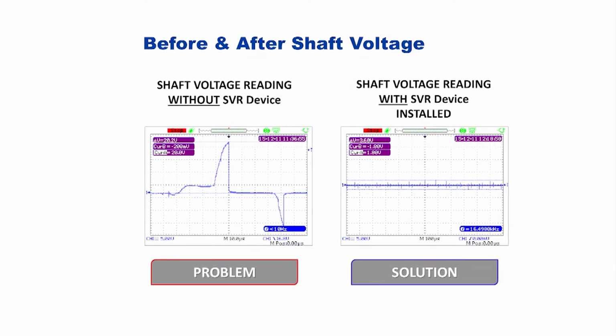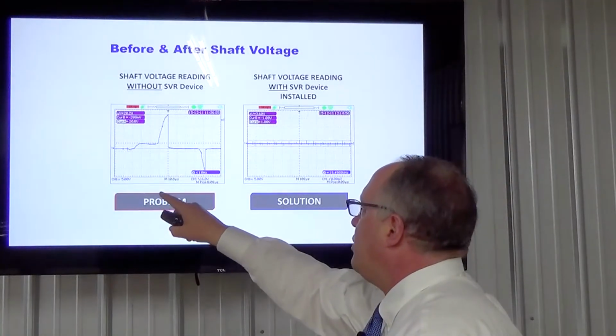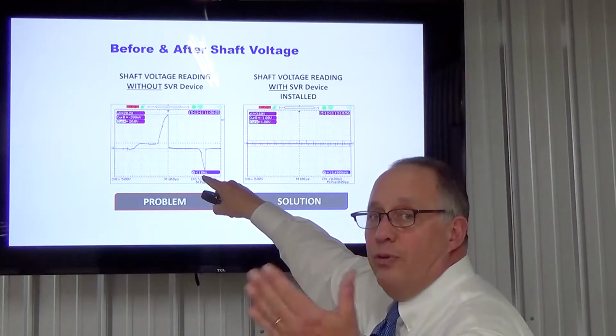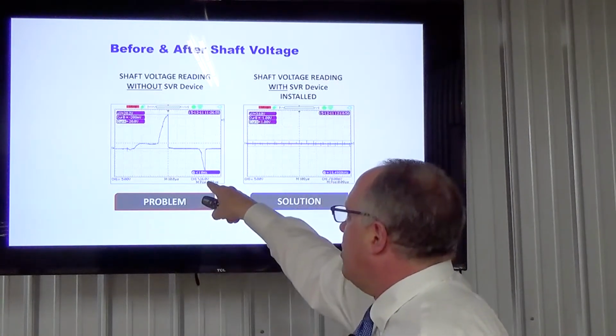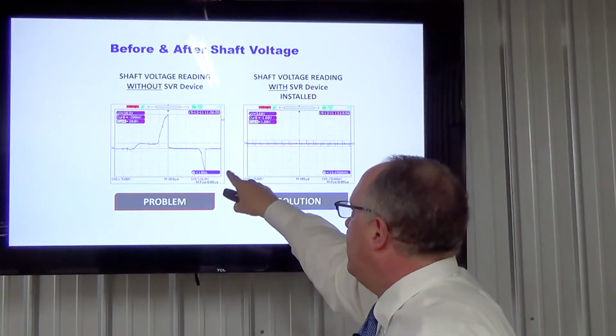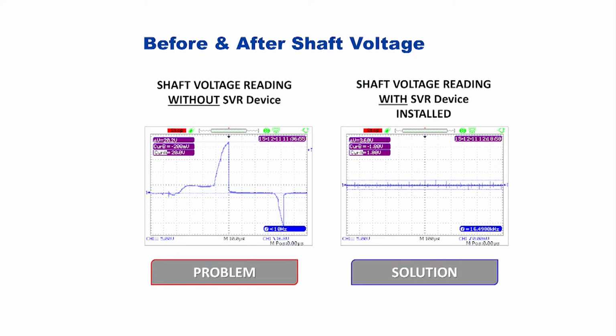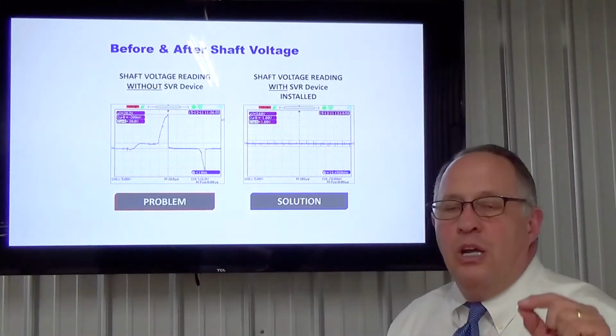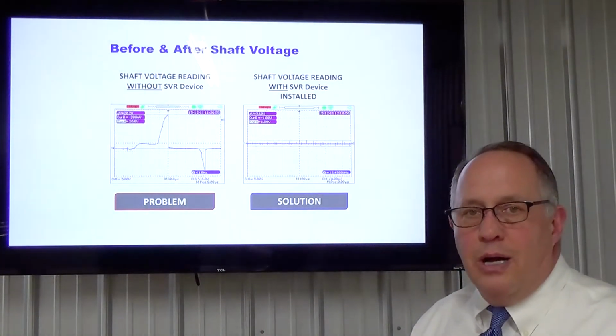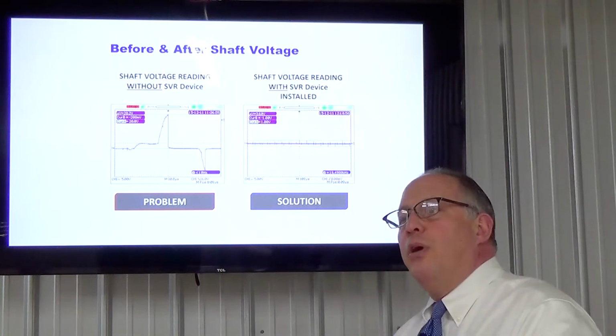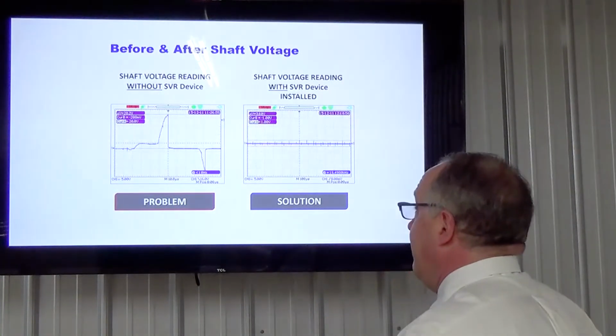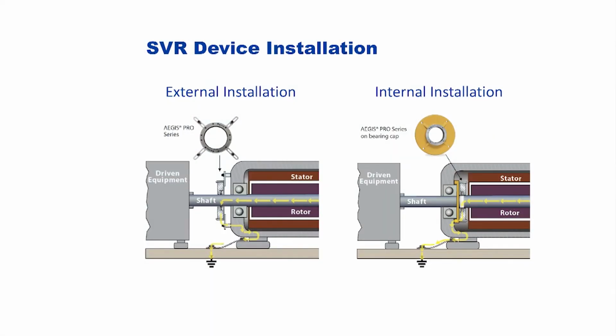Before and after shaft voltage. Over here on your left is a problem. Remember back when we saw the buildup of voltage in that shaft on every single cycle? It peaks and then it quickly discharges down to zero. That's the point at which we get the arc. And then on the opposite part of the wave, the negative sequence, it also arcs and goes to zero on that one, every single cycle. With the solution, with a shaft voltage SVR device installed, then you look at the voltage and it's essentially zero. You might have a little tick every once in a while where the shaft voltage was induced, but then it quickly bleeds off, providing a great solution with no damage to the bearings or to the motor.